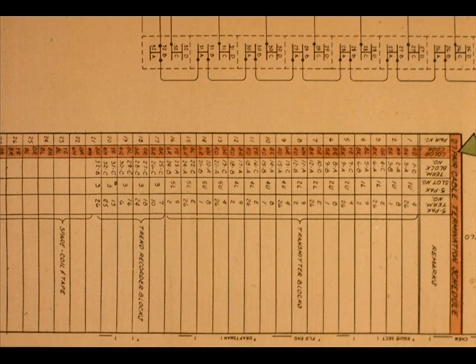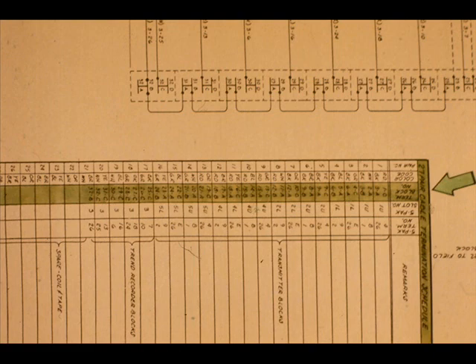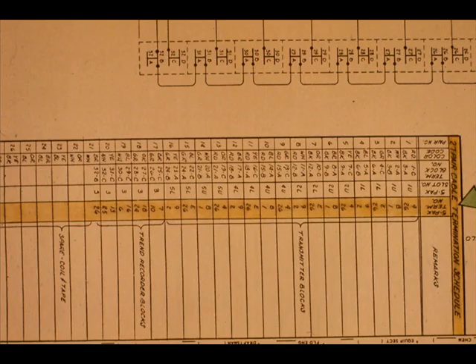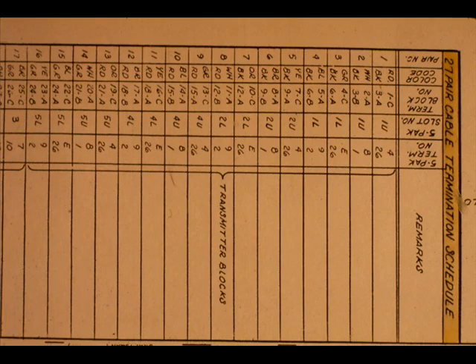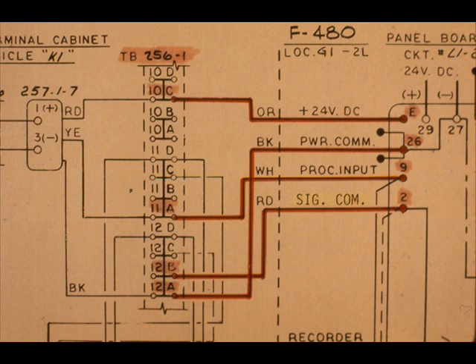You will have to use the cable termination schedule shown on the drawing. This information gives you the pair color code, the terminal block where the wires terminate, and the controller terminal where the other end of the wires terminate. The cable termination schedule is an engineering shortcut. The termination points of the cable are designated rather than drawn in schematic form. For instance, we need the wires that leave TB256-1 terminals 10C, 11A, 12B, and 12A.